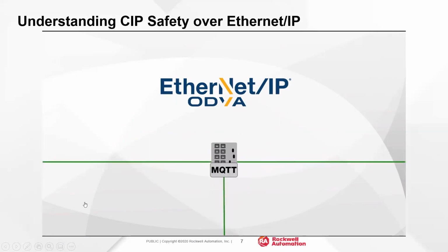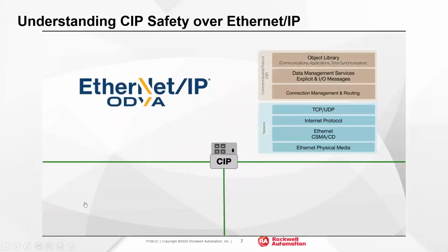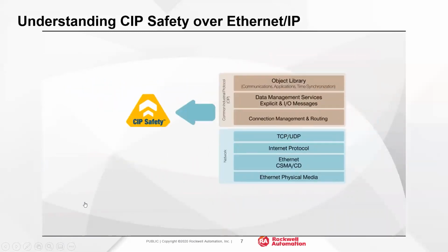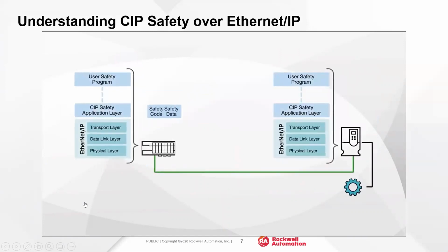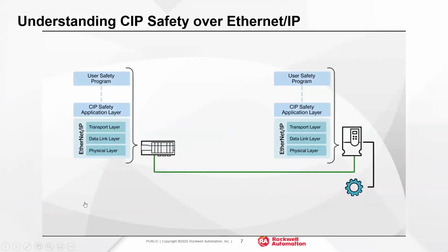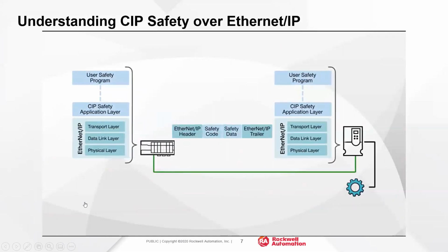Using the foundation of the Common Industrial Protocol, an open communications specification managed by ODVA. Because CIP exists only in the application layer of the OSI and TCP models, it is easy to add high-integrity safety services and diagnostics without requiring special communications hardware. This leverages existing communication infrastructure and helps reduce lifecycle costs. This enhanced protocol is called CIP Safety, and it can coexist with other application layer protocols like CIP Motion and CIP Security. Safety data in the device is packed into the CIP Safety protocol, which resides inside an EtherNet/IP packet, which becomes an Ethernet frame.